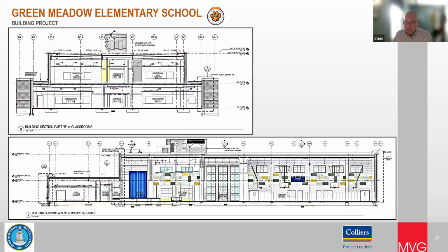So hopefully, Mike, that helps. There is a little bit of adjustment in the system. If you find continually that the building's so well insulated that you need less heat and more cooling, then maybe the set points are adjusted down the road to meet the district's needs. If that's the way the environment is going, and in 50 years you need more air conditioning than heating days, the system has the capability of providing both, but not simultaneously, where one room is air conditioned while the room next door is calling for heat. There shouldn't be that much difference room to room in the building.